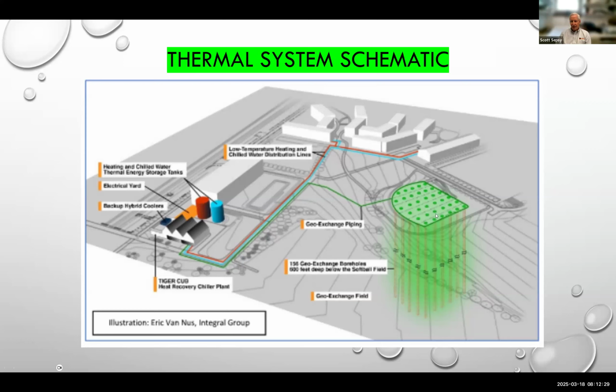What you see here is the geothermal well in the green, and they're 600 feet plus in depth. And the plants over here with the heat pumps, you've got hot water and chilled water storage tanks, and it's all the same water. It's just water that goes hot and cold, and the geo. We share the chemistry in those systems.